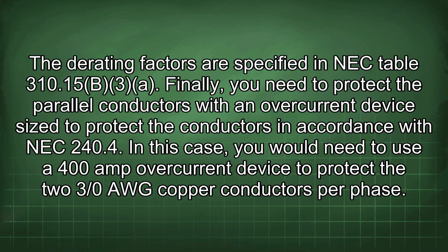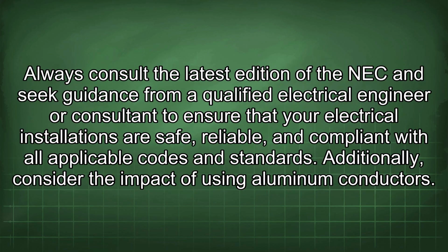sized to protect the conductors in accordance with NEC 240.4. In this case, you would need to use a 400 amp overcurrent device to protect the 2 3/0 AWG copper conductors per phase. Always consult the latest edition of the NEC and seek guidance from a qualified electrical engineer or consultant to ensure that your electrical installations are safe, reliable, and compliant with all applicable codes and standards. Additionally, consider the impact of using aluminum conductors.